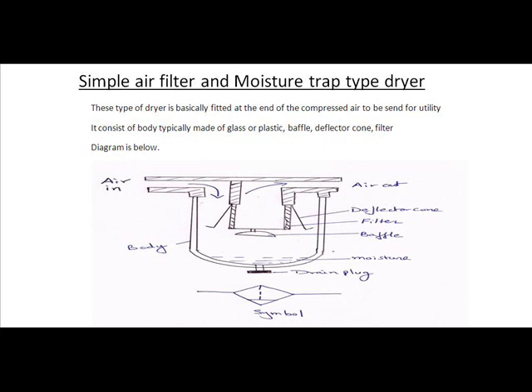How the air gets into the dryer and how the moisture is trapped: there is a deflector cone, there is a filter, and the air after getting through the deflector and through the baffle plate, the moisture gets trapped at the bottom. There is a drain plug through which the moisture gets drained and the air gets out which is cleaned and moisture free.